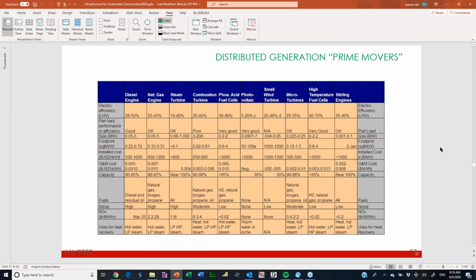When we look at our distributed generation assets that we might utilize, we see that they have different characteristics with regard to efficiency, part load performance, size, the amount of space required, the install cost, the operations and maintenance cost, the capacity, the fuels they use, the noise, the NOx generation, and the temperature at which they reject heat, which leads to what different types of end uses the waste heat can be put to. So when considering a combined heat and power, a distributed generation plant, we can look at all of these characteristics to decide what particular technology is appropriate for what particular application.